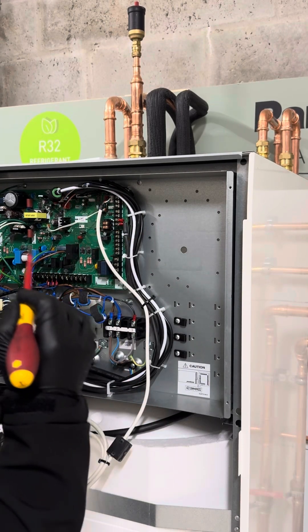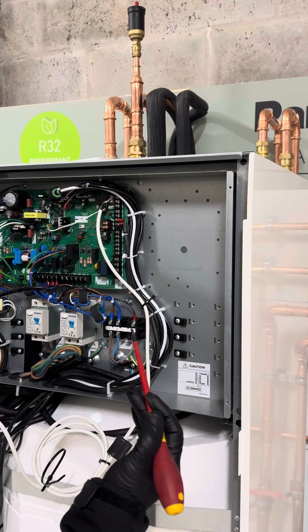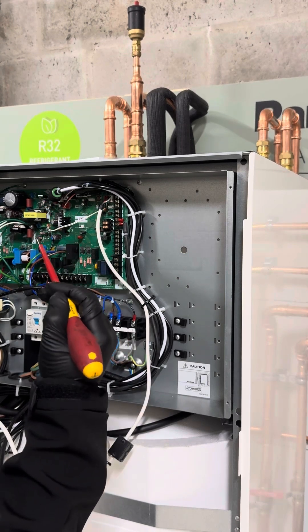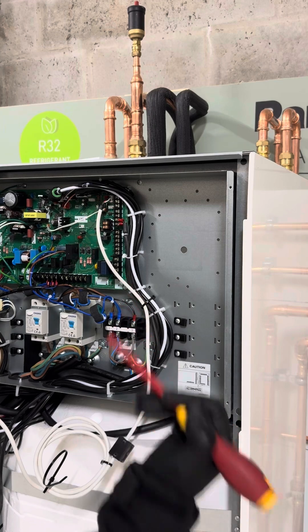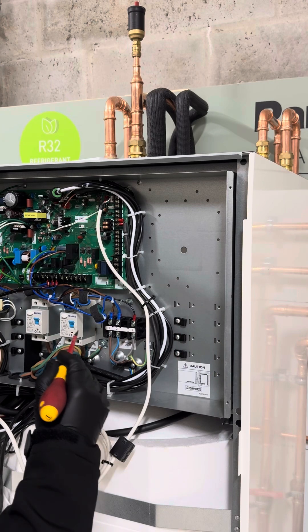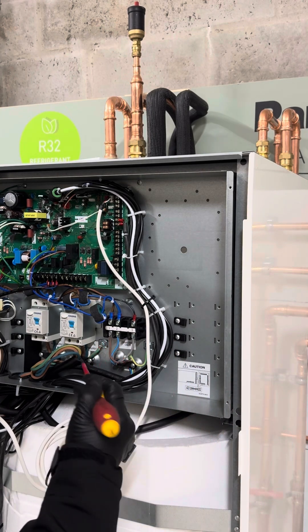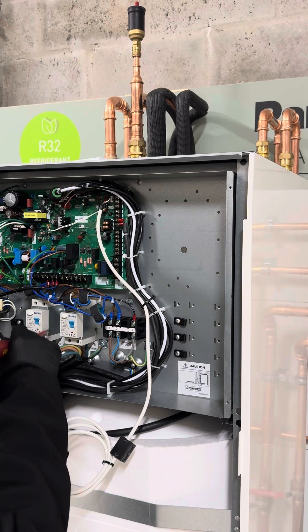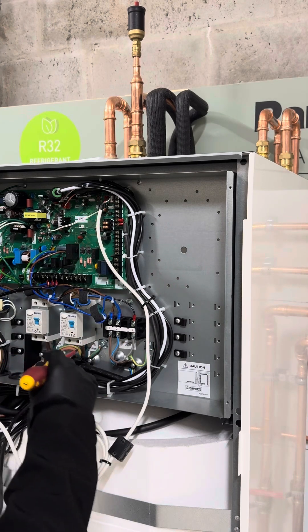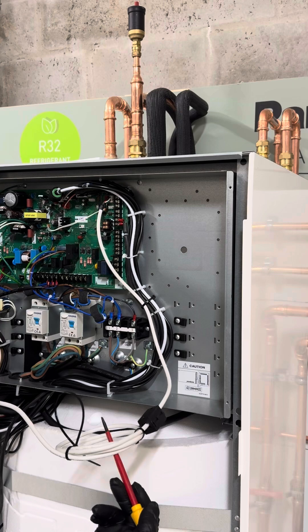From the consumer unit, two fuses — you may use, for example, six millimetre twin and earth — coming to your SCAME rotary isolation switches. From those switches, depending on the distance from the unit to the consumer unit, it could be four millimetre or 2.5 millimetre twin and earth at the electrician's discretion. That wires into the two breakers, giving power to the unit and to the backup heater. Then we have the interconnecting four-core, and the network adapter is clipped in and housed on the board.